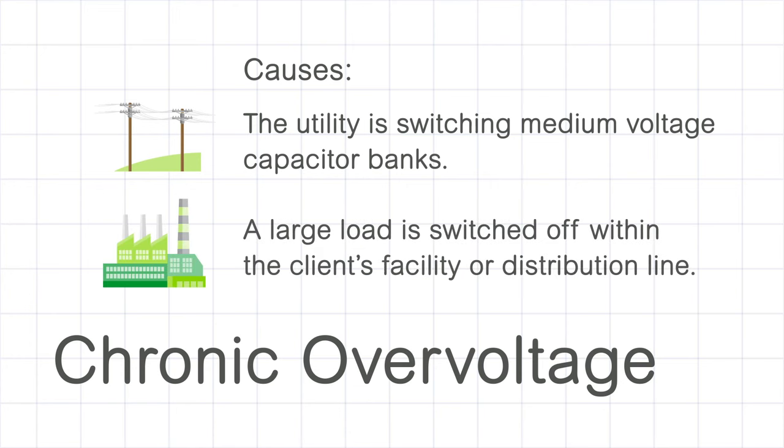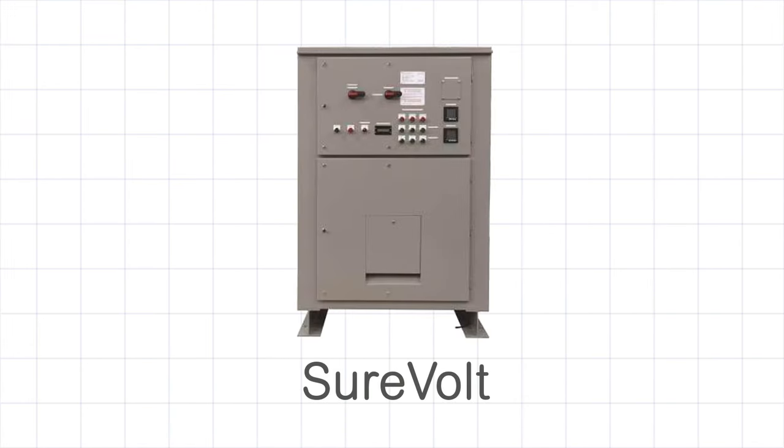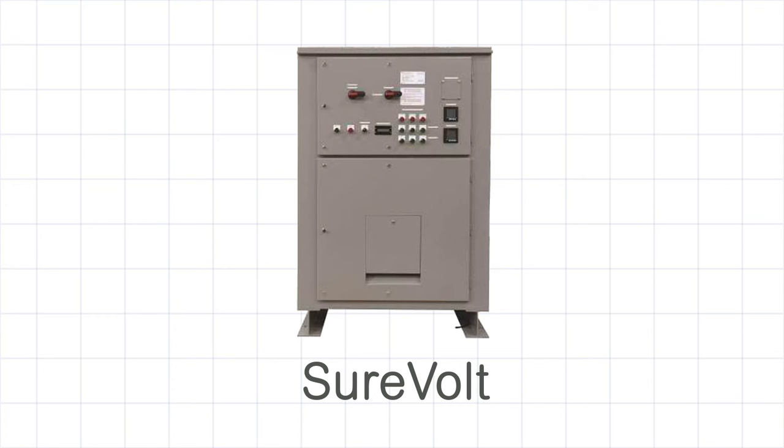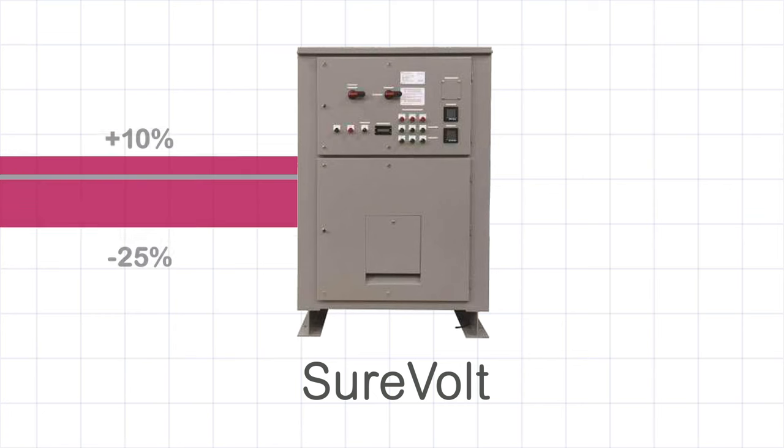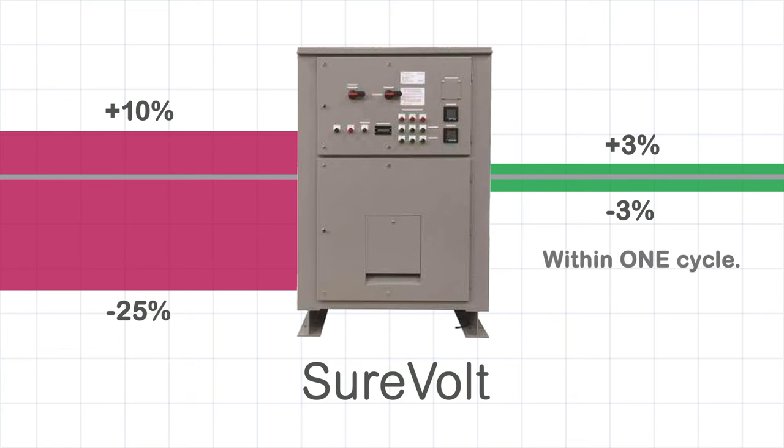A large load is switched off within the client's facility or the medium voltage distribution line. The SureVolt automatic voltage regulator can take a voltage input ranging from plus 10% to minus 25% and regulate the voltage supply to plus or minus 3% within one cycle, making it an ideal solution for chronic voltage issues.